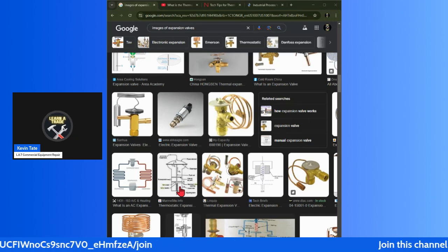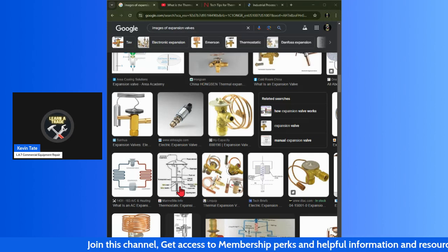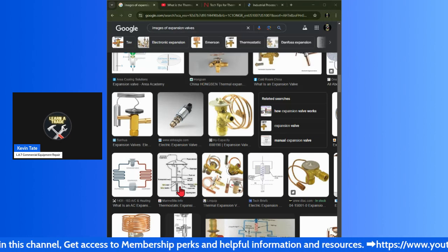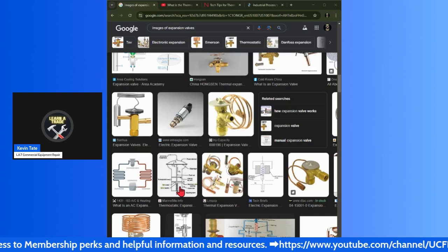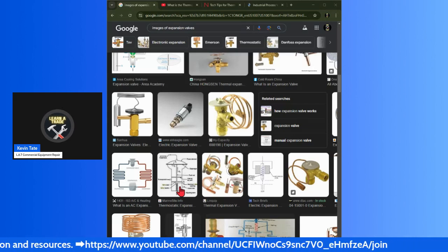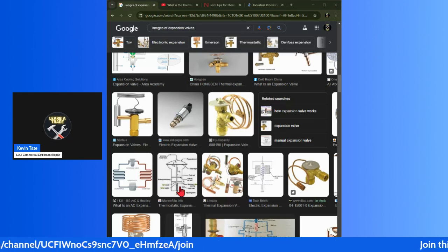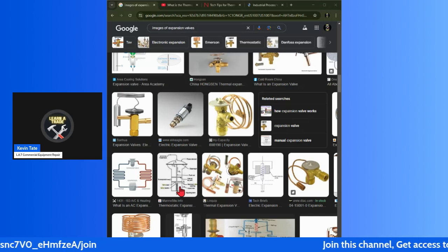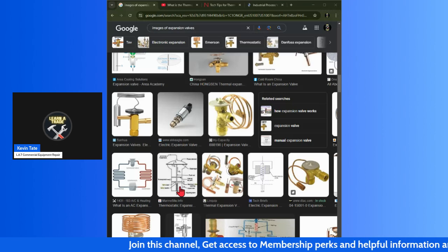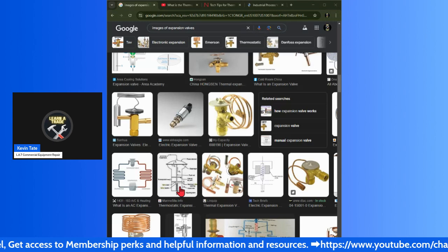If the evaporator of a water cooler, for example, were allowed to drop below 32 degrees Fahrenheit, it would freeze and potentially rupture, much like the water pipes in your home. To prevent this, automatic expansion valves are often used in these types of applications. They are adjusted so as to maintain an operating pressure several psi above the freezing point, thereby eliminating the need for secondary controls.